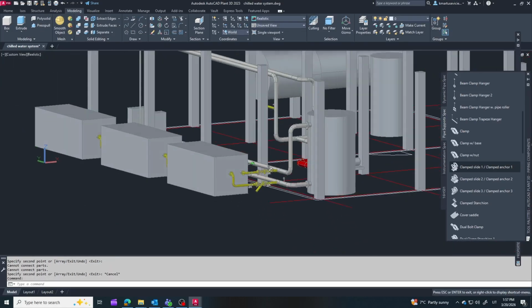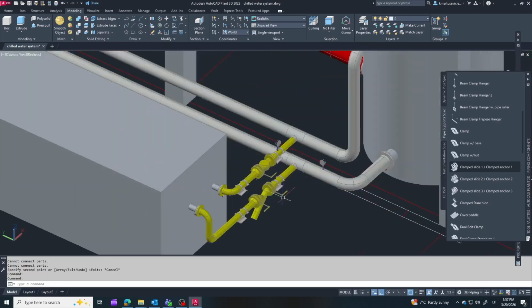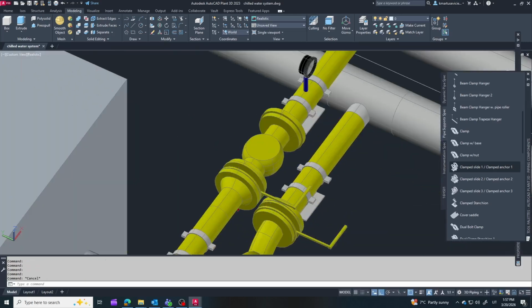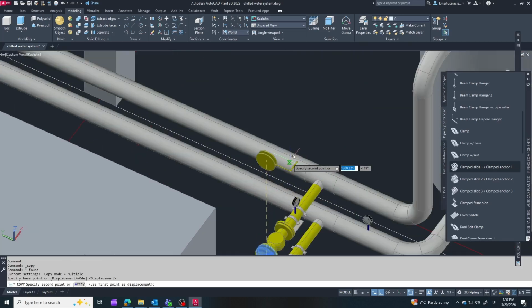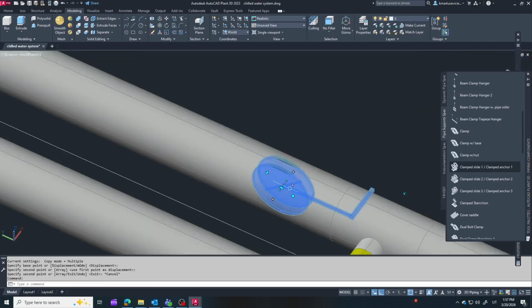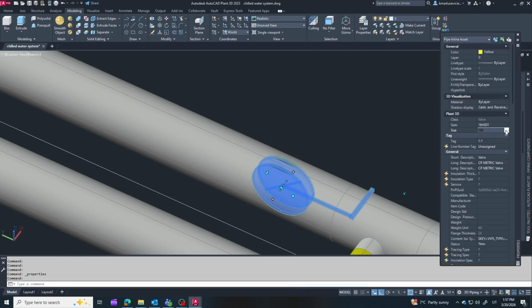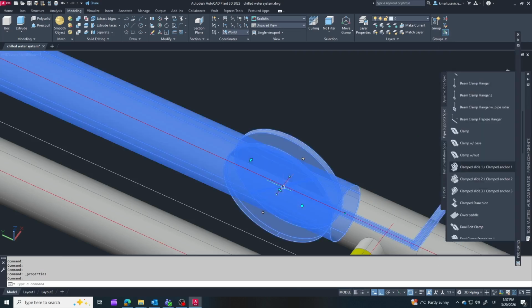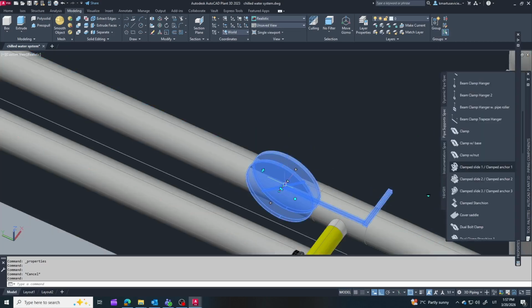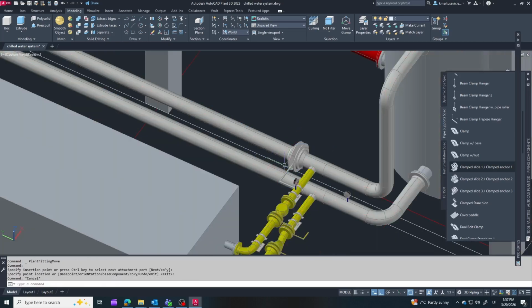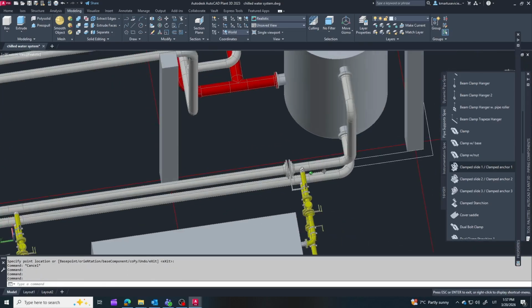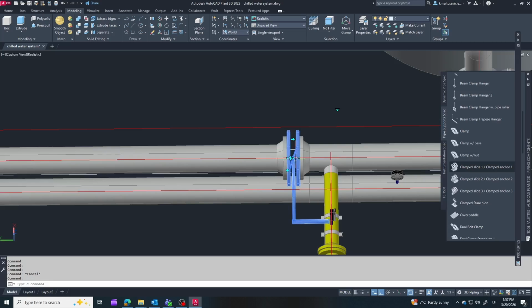I'm also considering adding isolating valves directly on the manifold. It's not strictly necessary, but it can be very useful. With these valves, we can isolate a single chiller without shutting down the entire system. However, DN200 is already a large pipe size, so these valves are not cheap. That's why we always need to evaluate the cost versus the actual benefit.